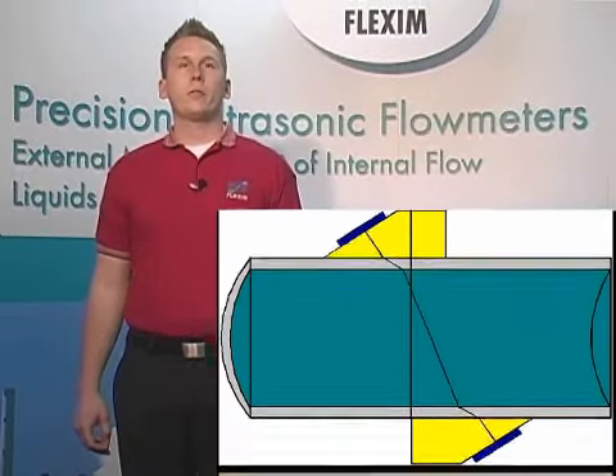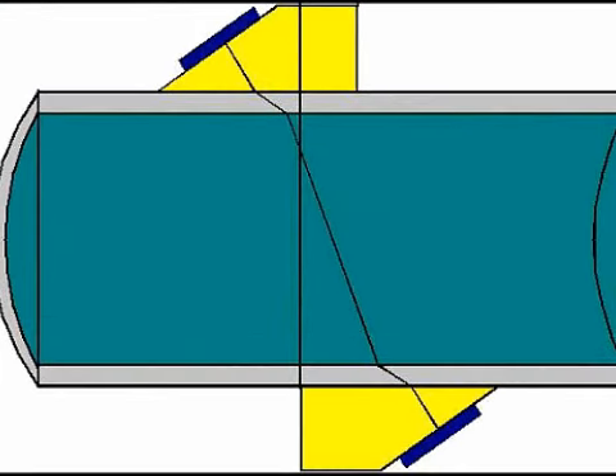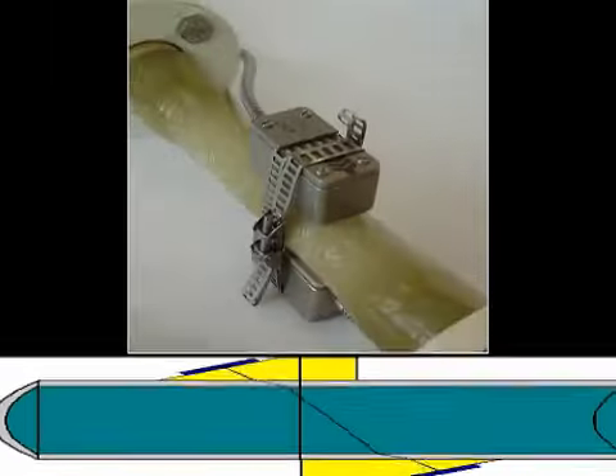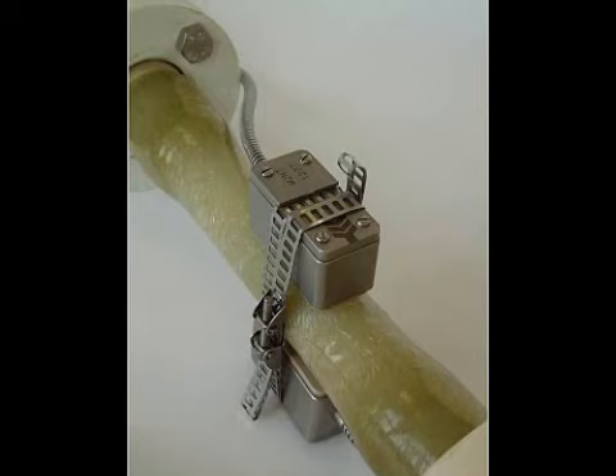Now, we're given a recommendation of the number of sound paths. Sound paths are the number of times the ultrasonic wave traverses the fluid. If the beam goes straight through the fluid once, we call this direct, or one sound path, and we must mount our transducers on opposite sides of the pipe. We call this direct mounting.